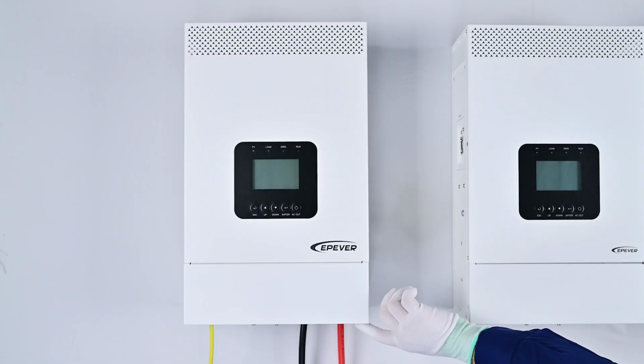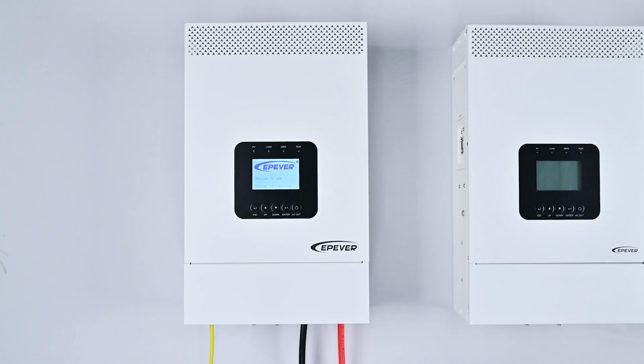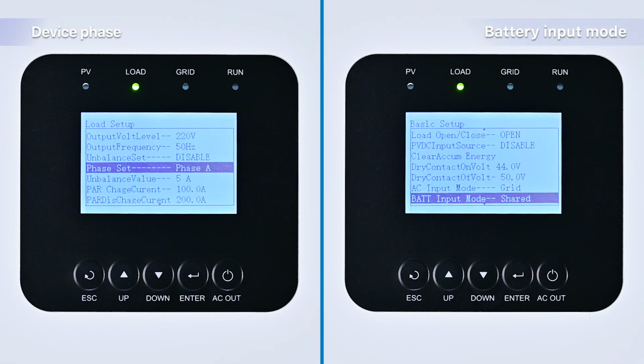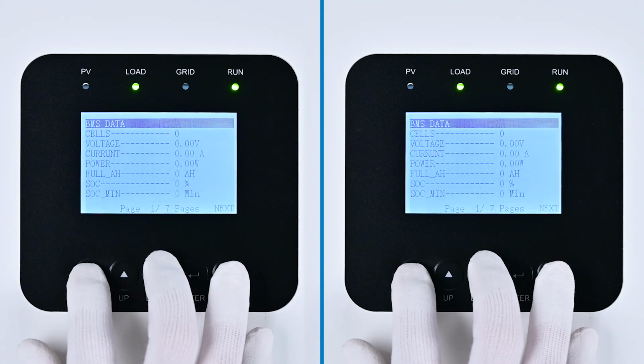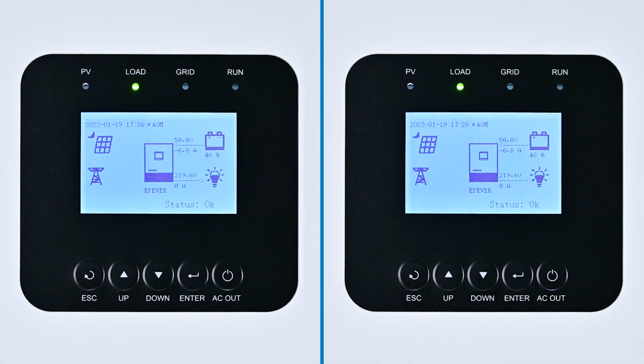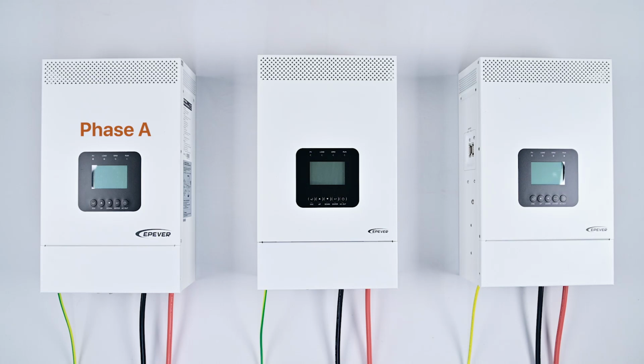Repeat the steps you've previously followed to verify the phase setting and battery input mode of the device. Ensure that the phase set is correctly set to phase A, and the BAT input mode is set to shared, indicating successful configuration of both settings. Press ESC to exit and then power off the device, removing the battery. For the remaining two devices, apply the same procedure, setting their phases to phase B and phase C, respectively. Ensure the battery input mode is consistently set to shared across all devices. Power on these devices again for confirmation.